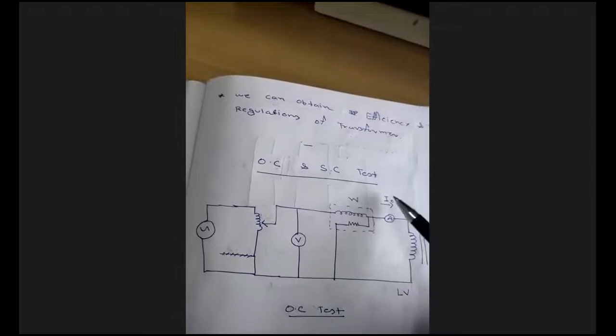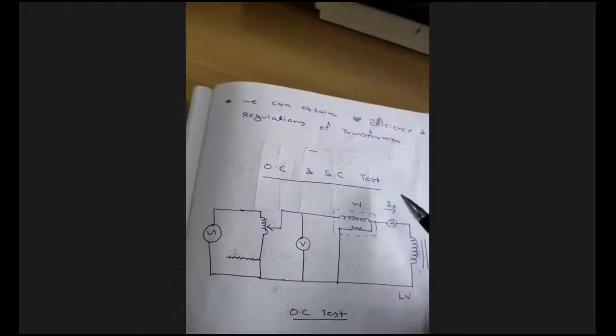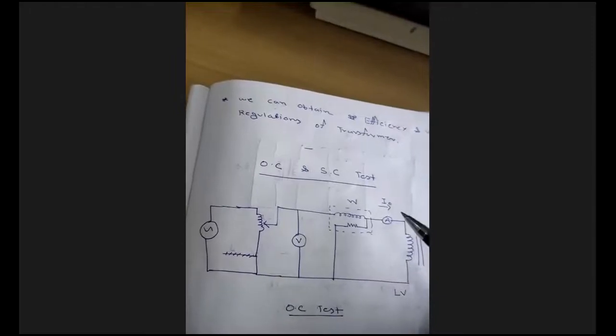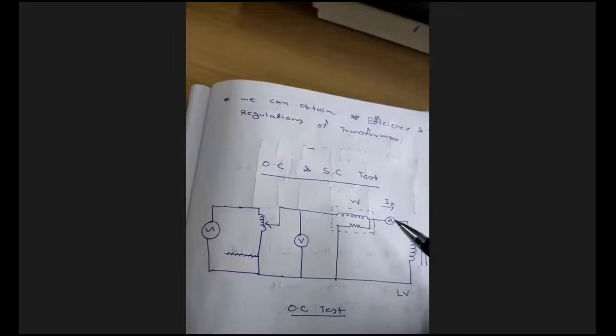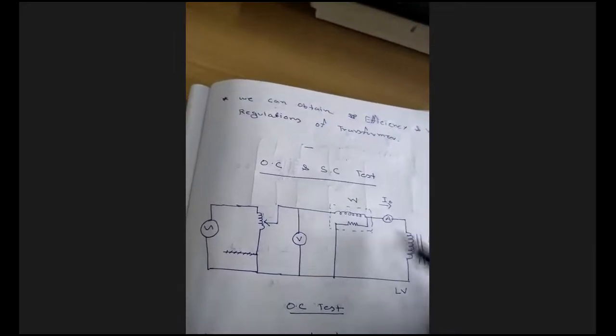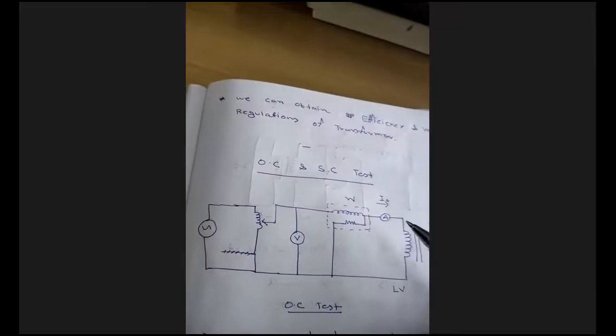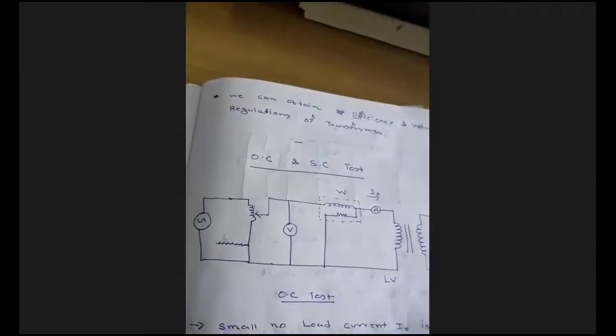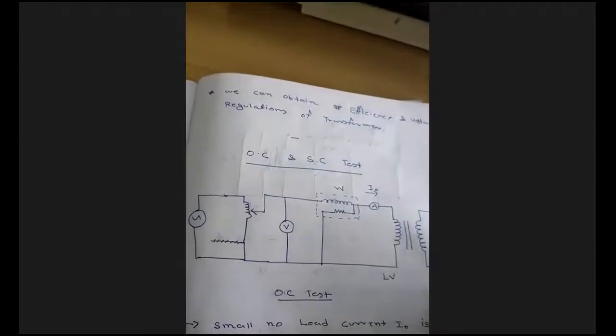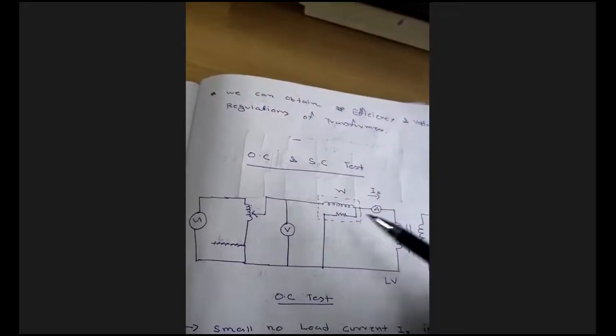इस करंट, ये जो करंट फ्लो हो रहा है लो वोल्टेज साइड में, ये करंट का वैल्यू क्या होगा, वेरी स्मॉल होगा. ओके, बहुत कम होगा. यूजुअली इट इज बिटवीन 2 to 5% ऑफ द फुल लोड प्राइमरी करंट. ओके, अगर प्राइमरी करंट मान लो 20 एम्पियर हुआ तो इसका 2 to 5%, 20 एम्पियर बहुत ज्यादा मैंने बोल दिया, तो प्राइमरी करंट जितना होगा, अगर 20 एम्पियर होगा, इसका 2 to 5% करंट इधर से फ्लो होगा.